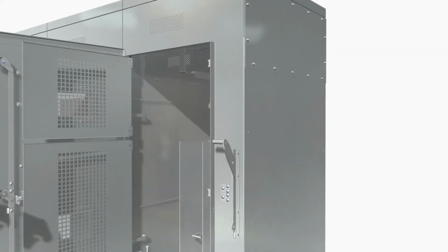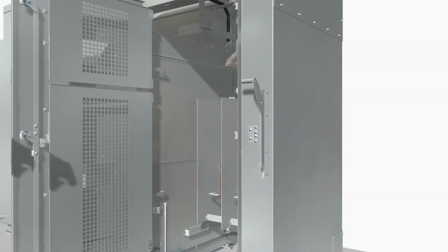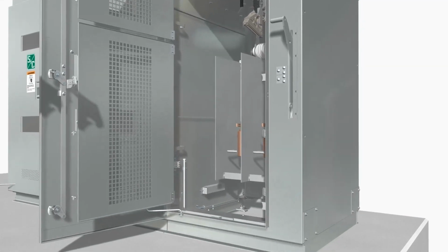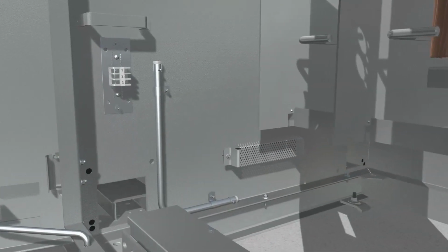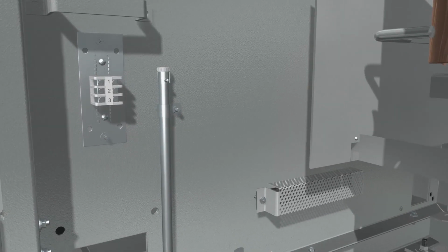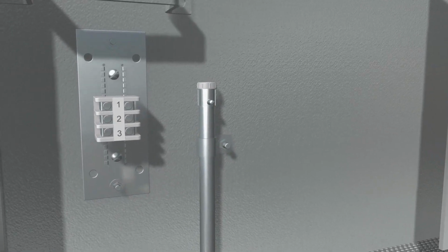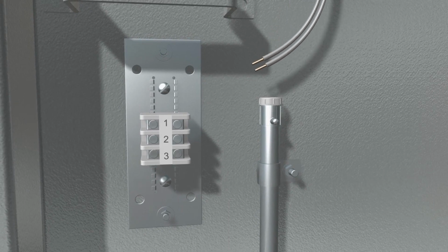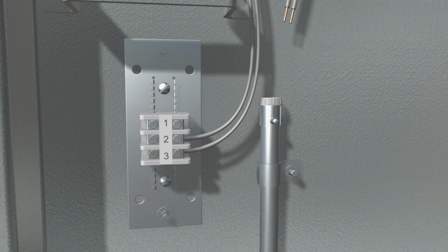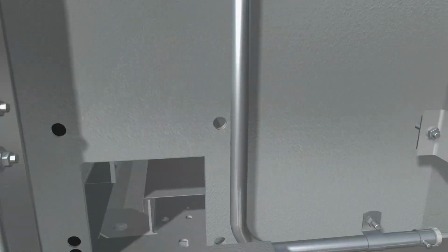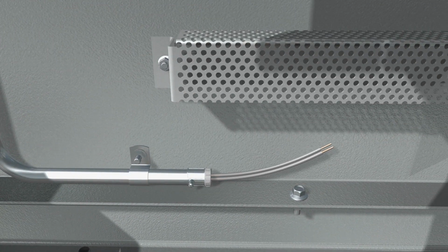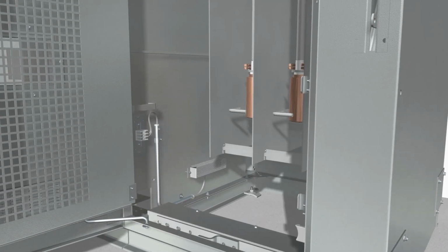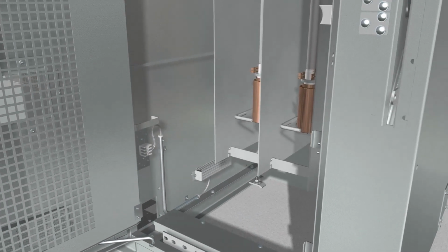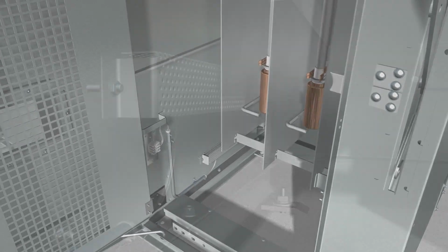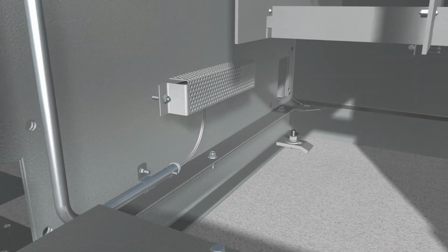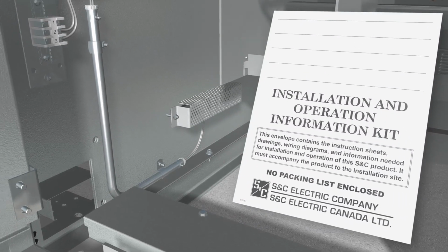Step 11. If secondary and control wiring are present, all terminals should be checked for tightness. Also, connect secondary and control wiring between adjacent bays at points where shipping splits occur. The individual wires at terminal blocks are marked to correspond with the adjacent terminal block marking. Connection of the secondary and control wiring should be checked with reference to the applicable CDR, QCDR, or CDT wiring diagram included with the Installation and Operation Information Kit.